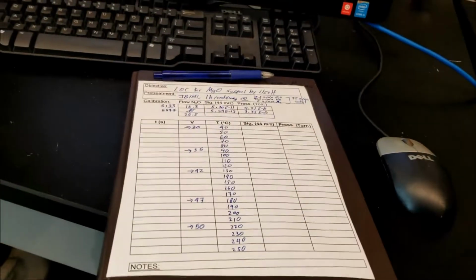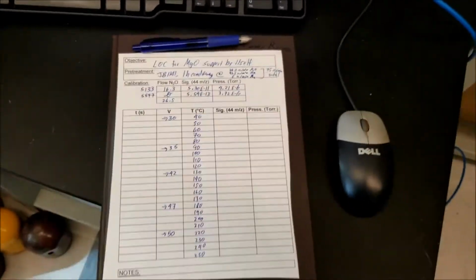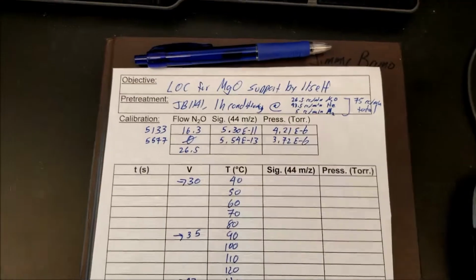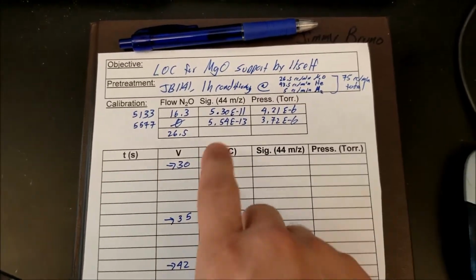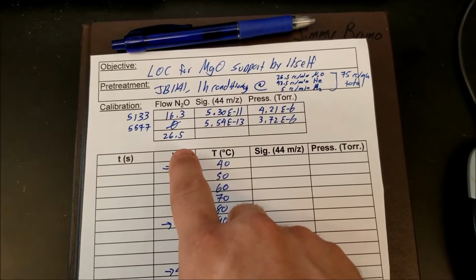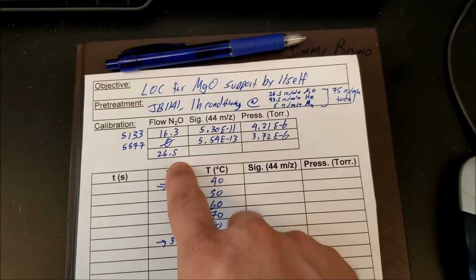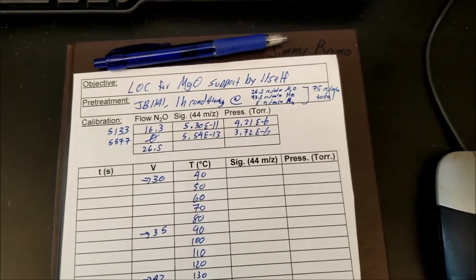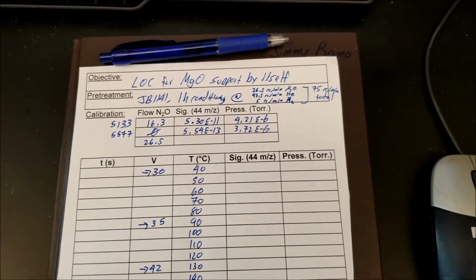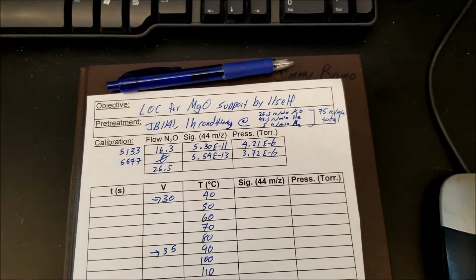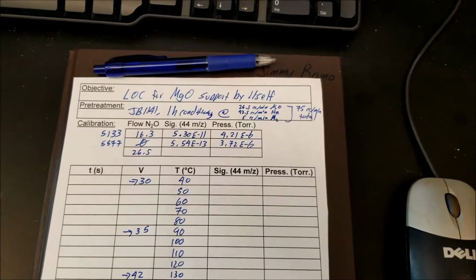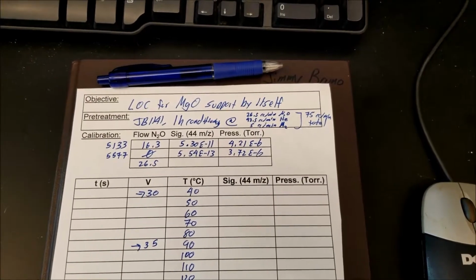So if we look at the calibrations, this is the data sheet for the light-off curves. And I have a section here for the calibration. You want to take 3 points. So 2 of those points should be familiar from what was done in the N2O video. Since we have 26.5 mils a minute, we did the calibration point at 16.3. You also want to take a calibration point when you turn off the N2O and make up the difference with helium. So it was 70 for helium and 5 with hydrogen. And that's because you want to know roughly where 100% conversion takes place, or when you've decently approximated it.